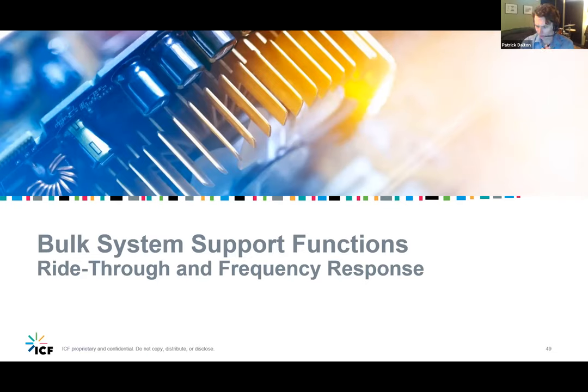Question: how do we handle unbalanced grid voltage regulation problems with inverters? The short answer is that inverters aren't going to help with that, or at least the standard inverter functions won't. Three-phase inverters are going to have identical three-phase response in terms of reactive power injection or absorption. So as a default right now, they're not going to help with phase unbalance at least. So, you know, one phase is higher than the other two phases, which is typically a sign of uneven loading or maybe a single phase capacitor bank, or there's a number of reasons, but in short, it really won't help.